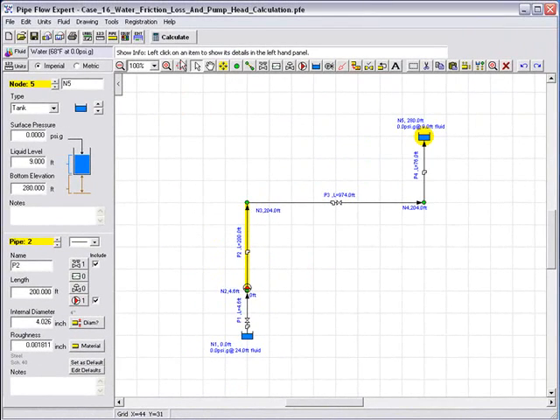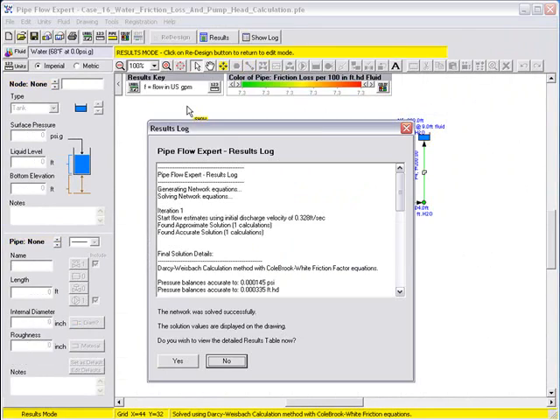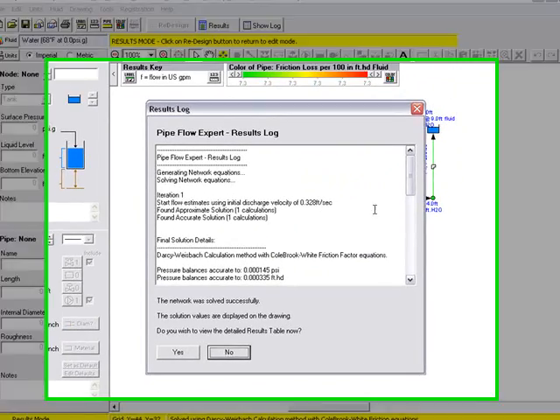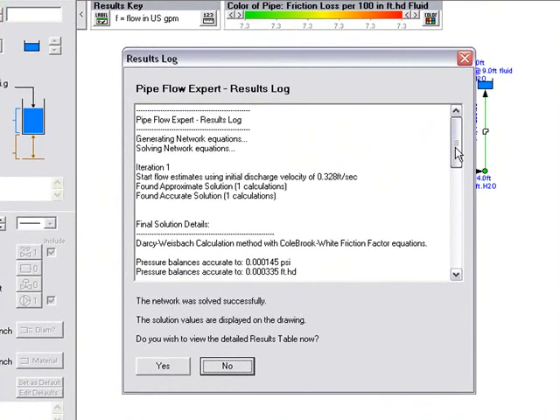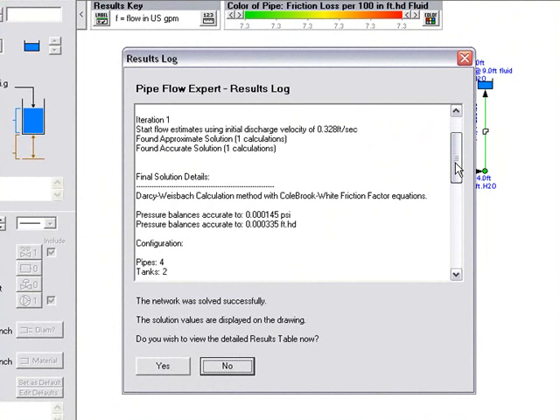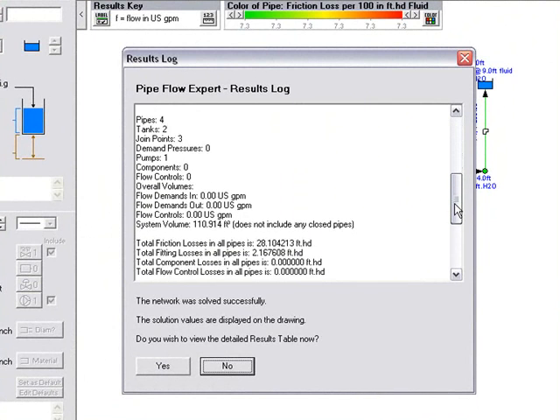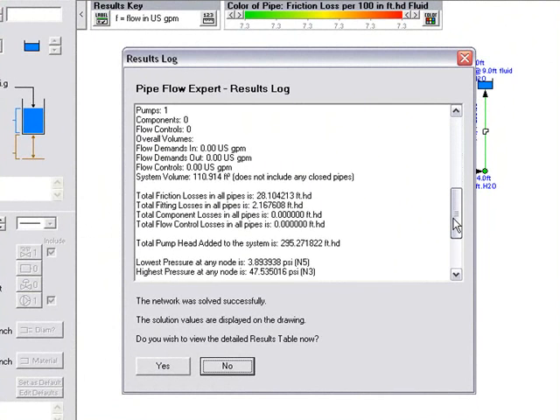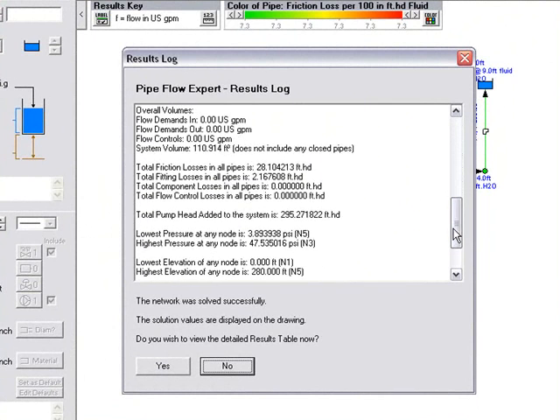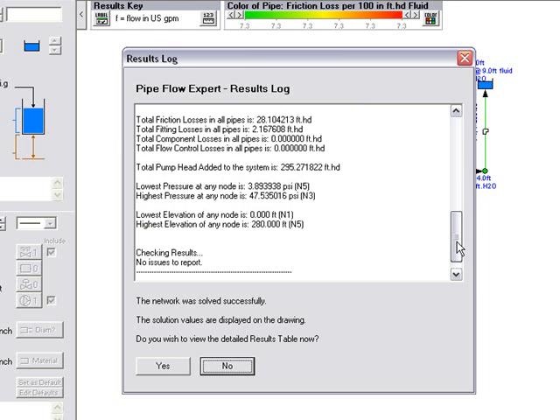If we run the calculation, we click on calculate. The system is solved and we can review the log. This gives us some information about the method used to solve the system and gives us information about friction losses and fitting losses. We can also see that the total pump head added to the system is 295.27 feet head. There are no issues to report. And we are asked, do we wish to view the detailed results table now?